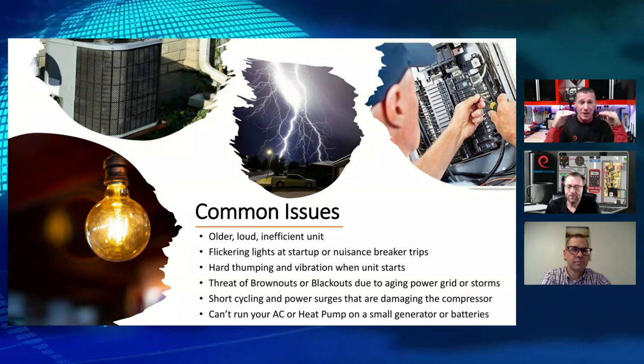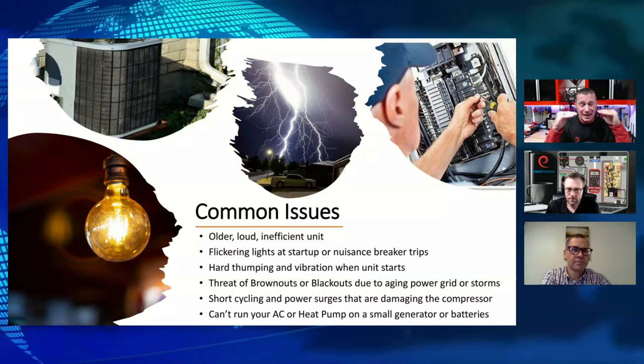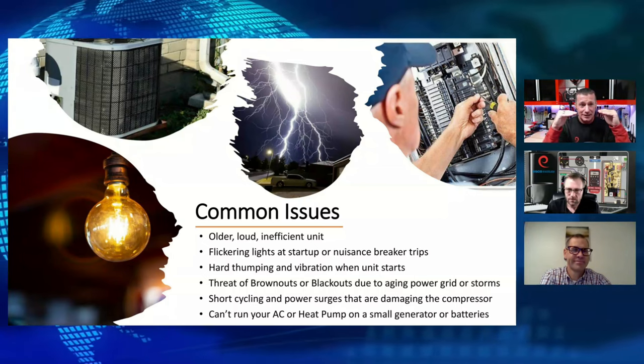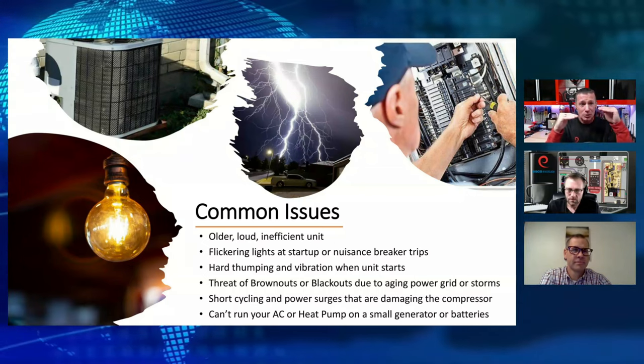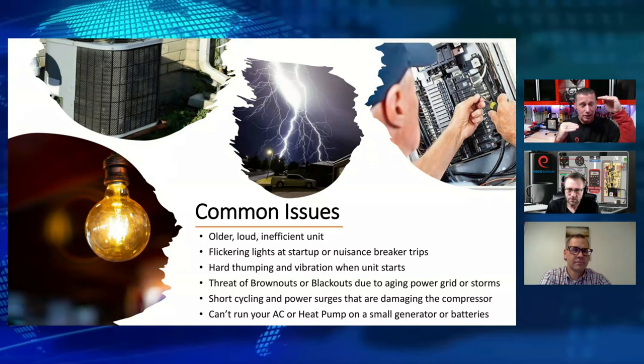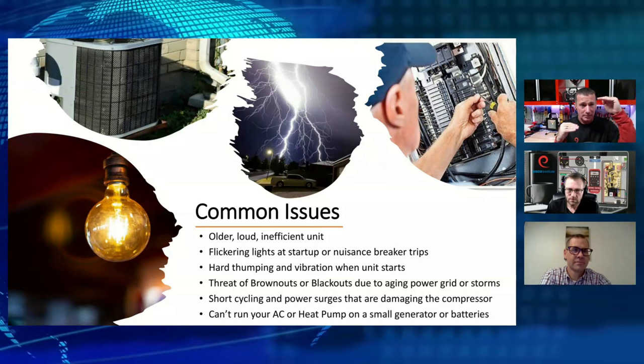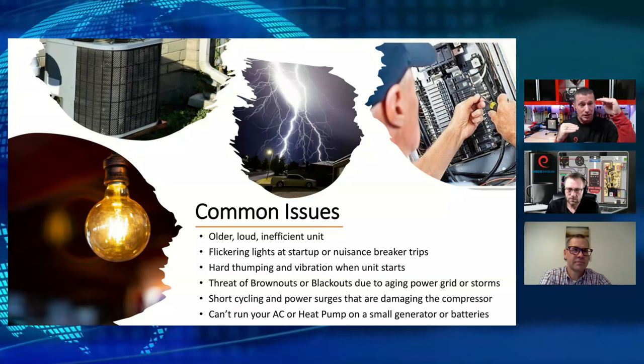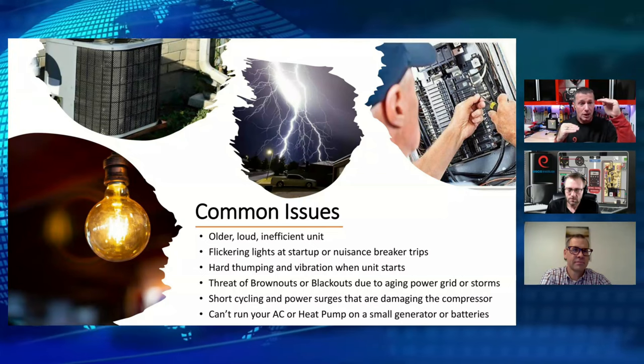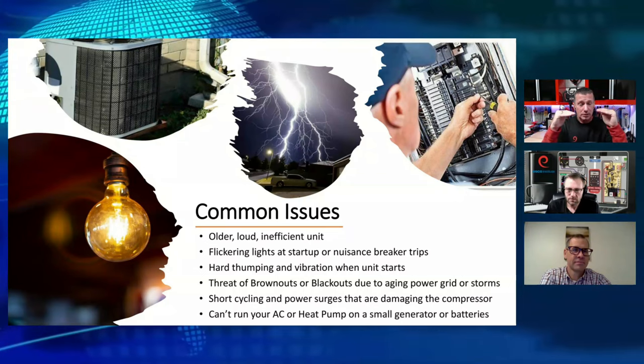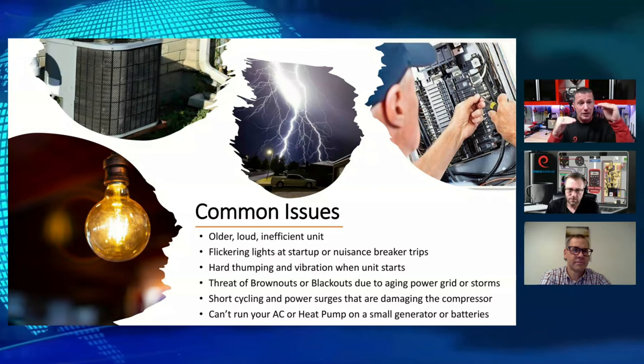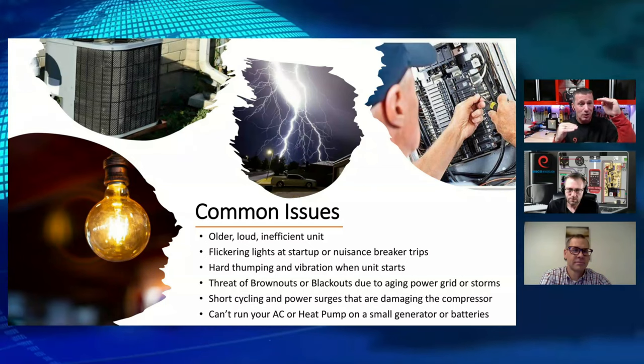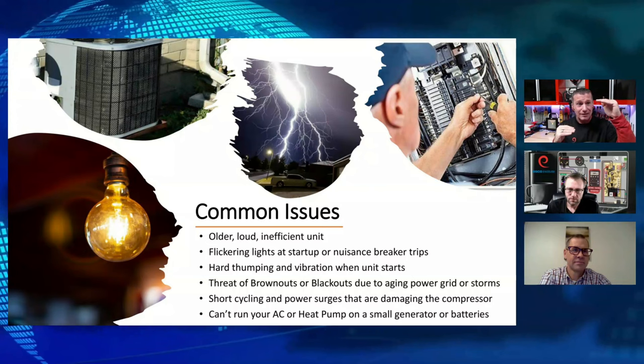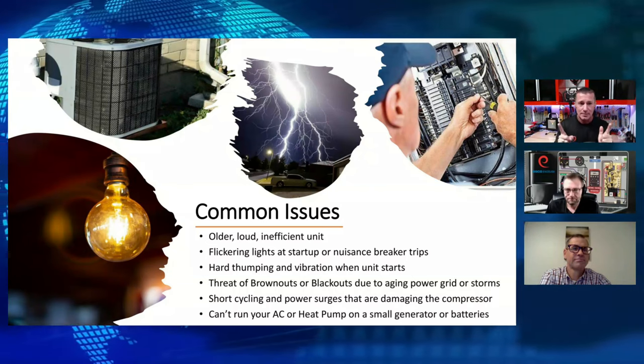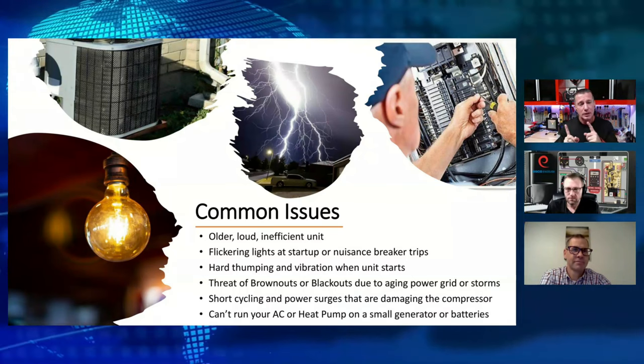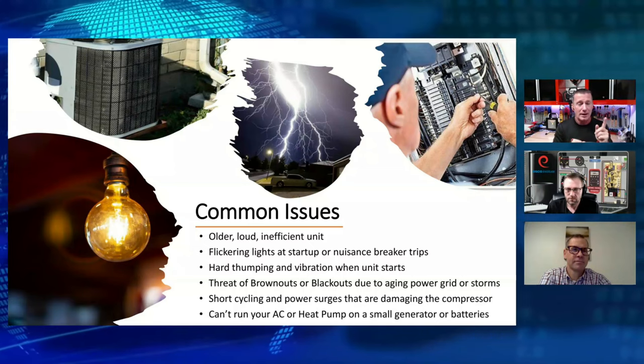Remember, with Ohm's law, if I've got 47 amps right now at this voltage, and my voltage goes down, the required current to keep the same momentum and force goes up. So 240 volts at 47 amps — if I drop that down to 160 volts, my 47 amps turns into 70 or 80 amps. Absolutely, we can have compressor issues from brownout scenarios.